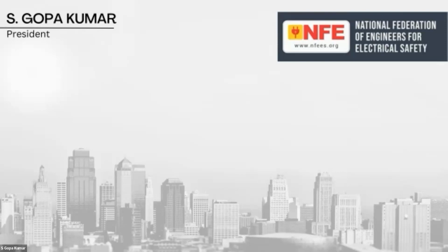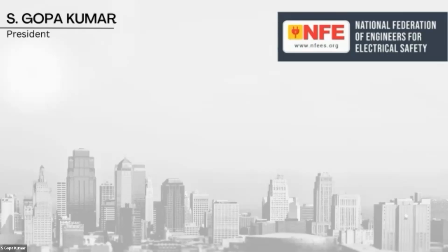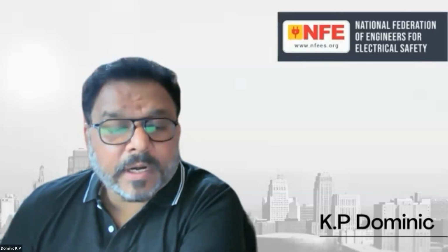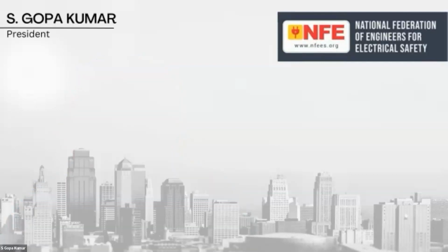This is your violation number 2, because earthing has to be outside the building, not inside your building. But IEC 62305 is allowing the pile as the earthing, right? No, IEC 62305 is not allowing it. It is allowing use outside the building structure. Oh, okay, let me look into that. John, you can write to Mr. Gopakumar. It is very clearly written that the earthing system, if you need, I can also show this clause to you. But it takes some time. If you can connect with me, then I can write to you and show you these clauses.